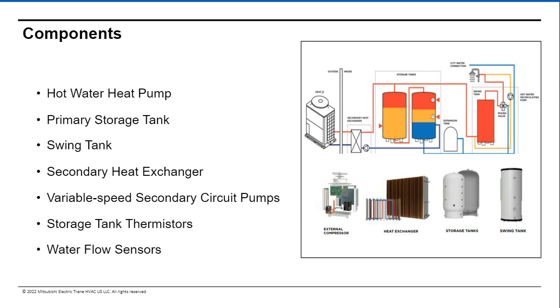Next we have our storage tanks. One of the big keys compared to traditional storage tanks is making sure we can keep good stratification in the tanks. You'll see the inlets and outlets of the storage tanks have what we call sparge fittings or baffles to redirect the incoming water flow in a perpendicular direction and also slow that flow down so you can keep good stratification in the tank. One of the really big keys to this system is being able to get cold water back to the heat pump. That's what it likes to see, and that's where it's going to run most efficiently.